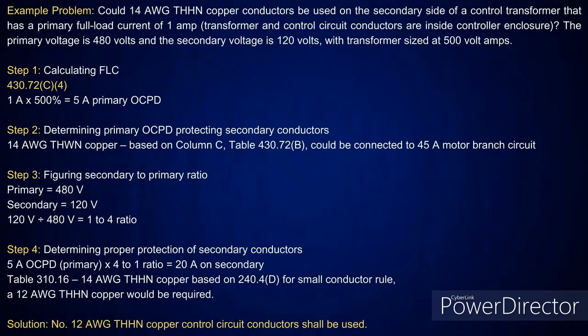Now, you'll know this one because we actually get into this where we're dealing with motors in 430.72(C)(4), and they're basically going to clarify exactly what you're allowed to do. All right. Now, when you come in, they're going to ask, could 14 AWG copper conductors be used on the secondary side of a control transformer that has a primary full load current of 1 amp?